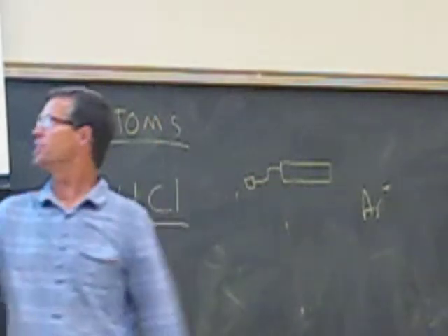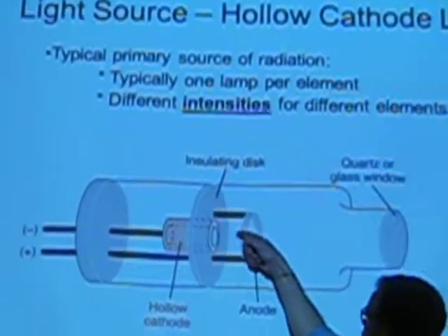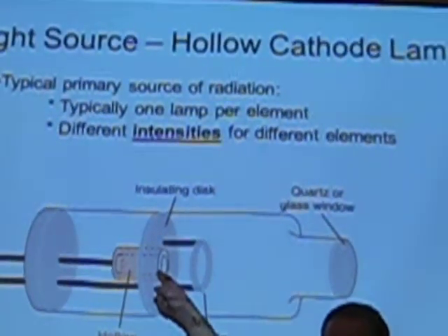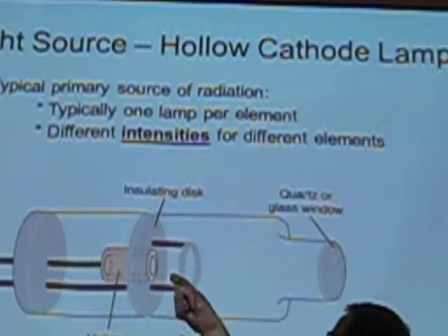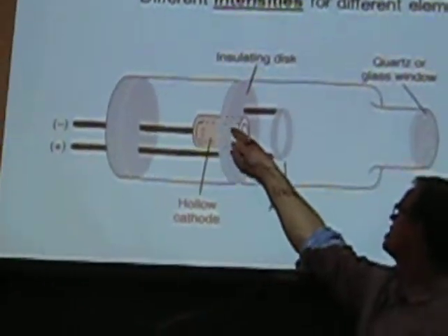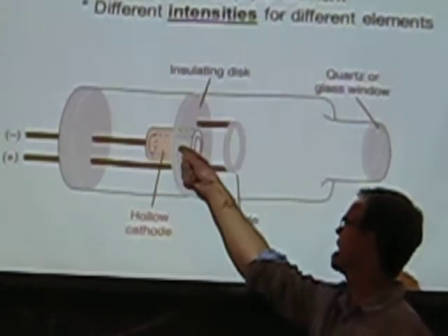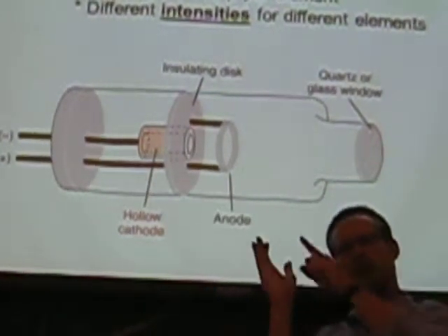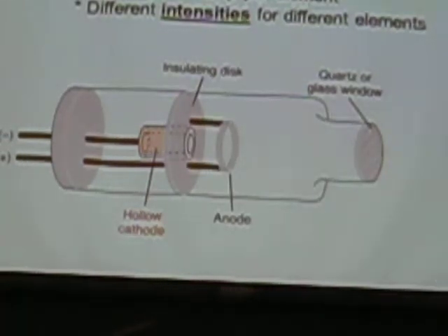Now those positive argon ions that are just here between the anode and the cathode get attracted to and accelerate towards the cathode, because this is negative. They accelerate, and those argon ions hit this cathode in the middle of this hollow tube, and they hit with such velocity that they sputter off a little bit of the metal atoms, in this case, the copper.